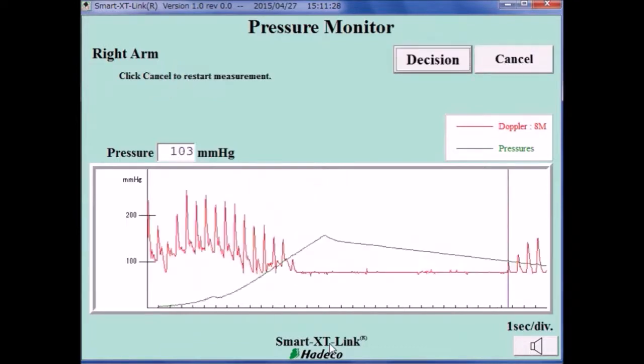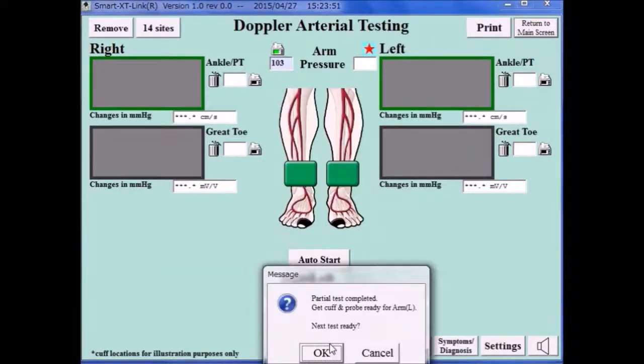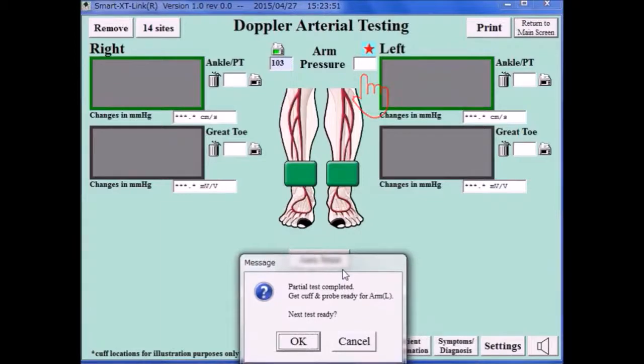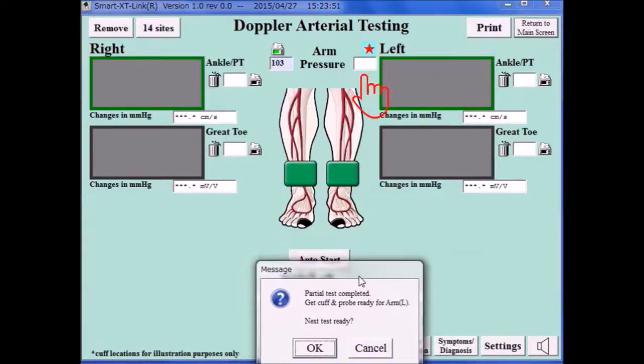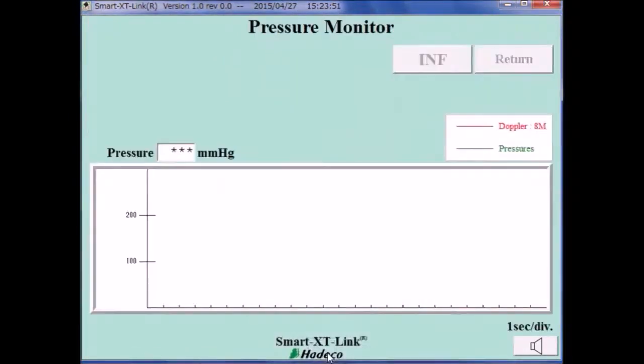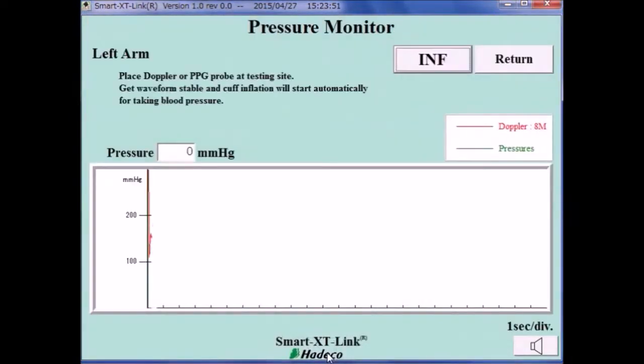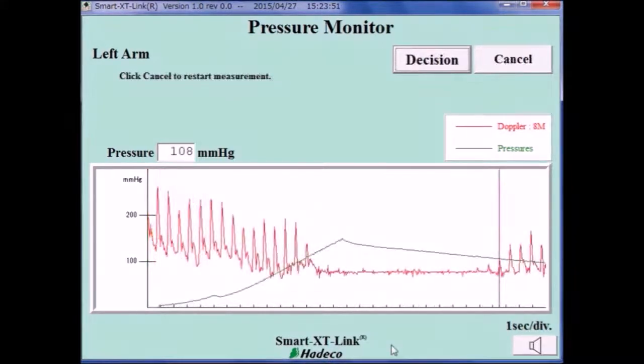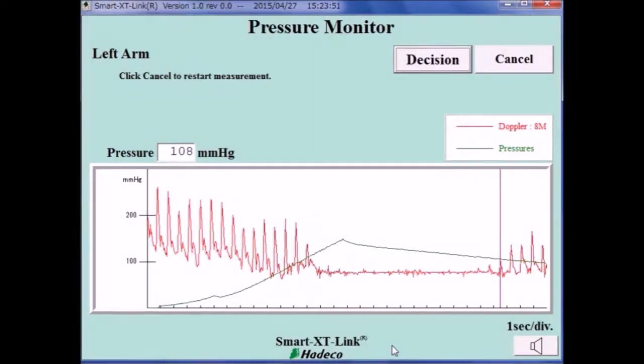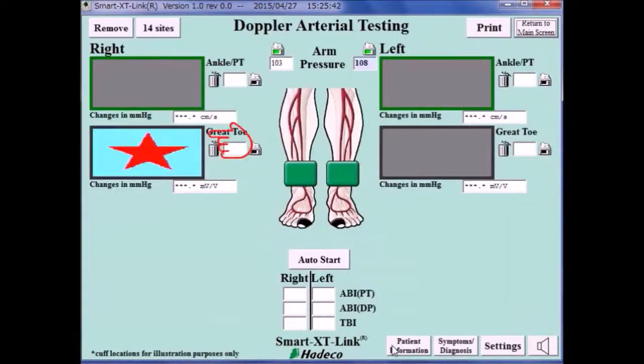After taking the right arm pressure, the XT will take the left arm pressure. Make sure the cuff and Doppler probe are ready for left arm pressure and click OK. After taking arm pressures for both sides, the XT will automatically take the waveform and then pressure on the right great toe with the PPG probe.